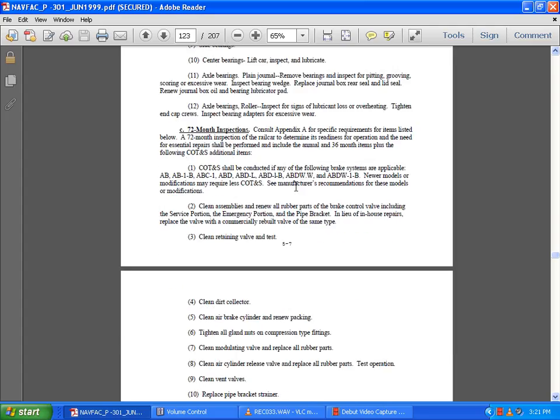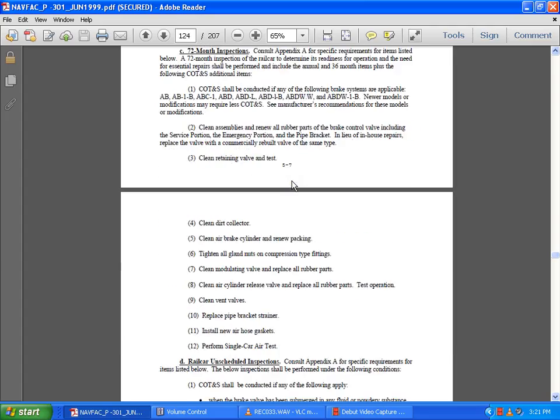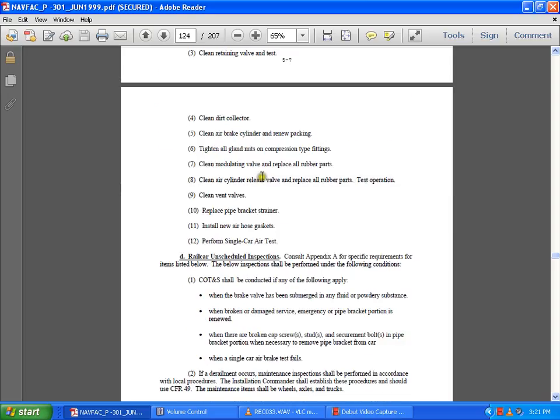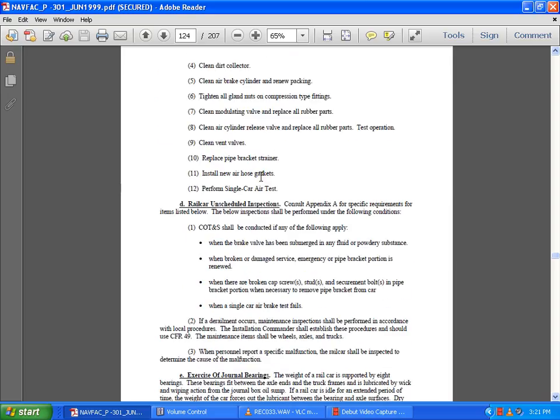Clean retaining valve and test, clean collector, clean air brake cylinder, renew packing, tightening all glands and compression type fittings, clean modulating valve, replace all rubber parts, clean air cylinder release valves and replace all rubber parts, test operation, clean vent valves, replace pipe bracket strainer, install new air gaskets, perform single car air test. Unscheduled inspections require consulting Appendix A specific requirements and items listed below, and the following conditions.